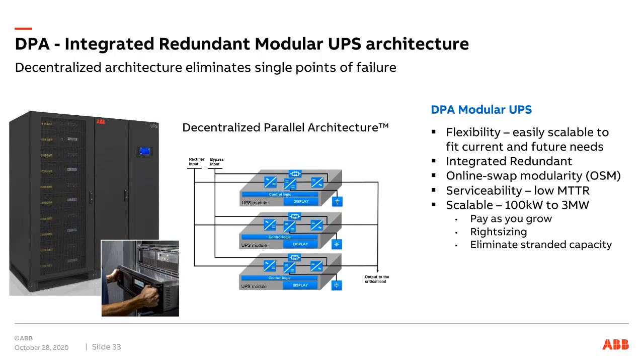And then, of course, the benefit with the ABB modular UPSs is the same as any other modular UPS. It's the flexibility, that you can easily scale. You can add modules as needed. You can slide in additional modules if a module should have a bad day, and like I said, anything man-made will fail. The UPS will tell which one it is. The control will tell which one it is, and the repair time, or mean time to repair, is minutes instead of hours with a monolithic type design.